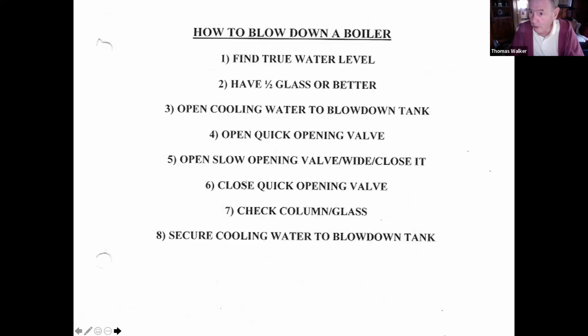The procedure I told you, you're really going to need this for the oral exam, but they've taken parts of it and they'll ask you on the written exam. For instance, one of the questions is, what's the first thing you do when you blow down the boiler? Well, you can see on the procedure, find the true water level. Or they'll say, when you get ready to blow down the boiler, which valve is open first? The quick opening valve. Which valve is open last? The slow opening valve. You get the idea. There are no provisions in a multiple choice test to ask you procedures. So the only way they know how to ask that is by asking parts of it.